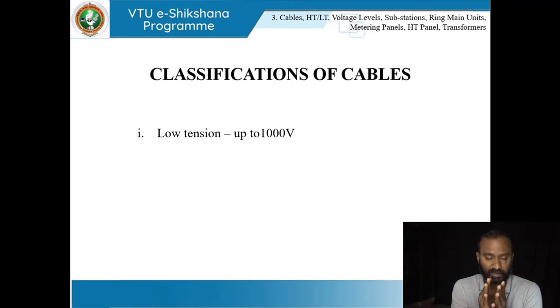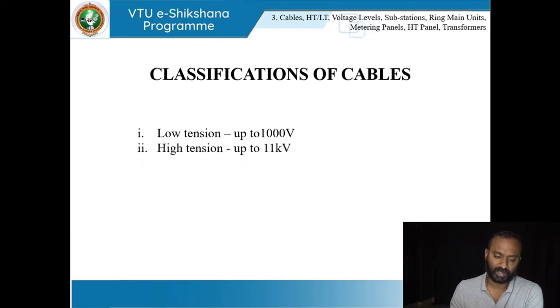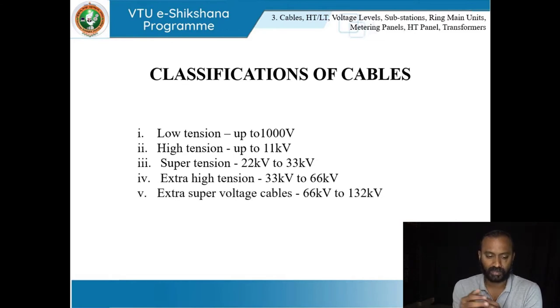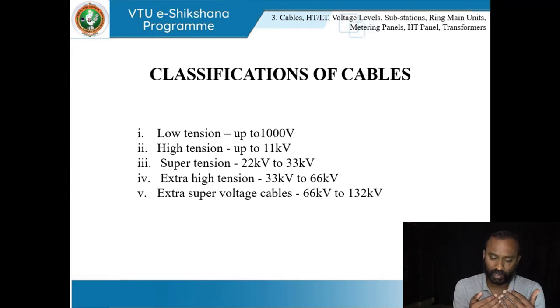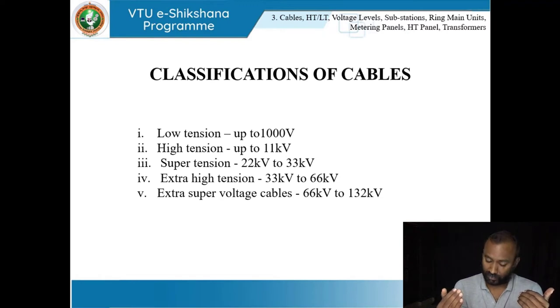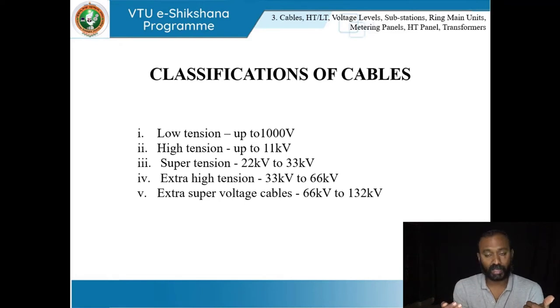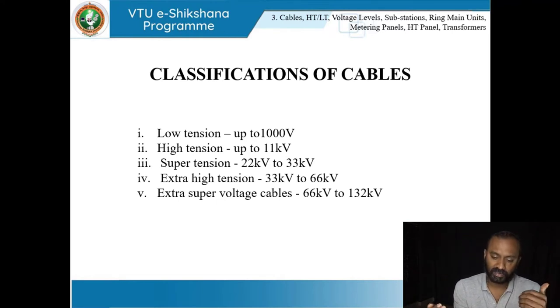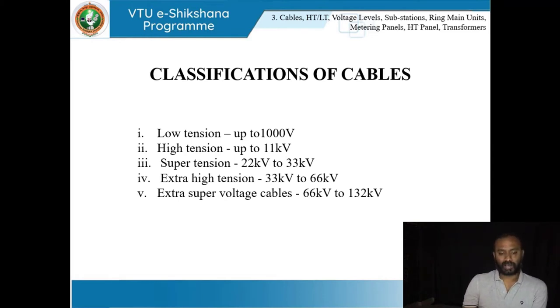Moving on to classification of cables: there are five classifications based on voltage range. Low tension is up to 1,000 volts (1 kV). High tension is from 1,000 to 11,000 volts. Super tension ranges from 22 kV to 33 kV. Extra high tension is from 33 kV to 66 kV. Extra super voltage cables range from 66 kV to 132 kV and further.